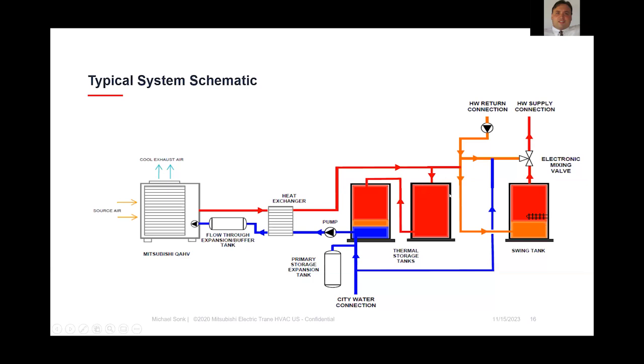So we would feed the hot water supply from this tank farm, if you will, that's been generated by the heat pump, and then into a swing tank. And that would have an electric resistance element that would provide that temperature maintenance during long idle periods. And so just like with any conventional domestic hot water system, you'd have a temperature mixing valve in that building and a heating hot water recirculation pump that would bring back hot water from the farthest fixtures to make sure you always have hot water primed out into the building. And again, the main goal here is to keep that off of the CO2 heat pumps and allow those to be utilized for what they've been designed optimally to be most efficient for, which is recharging these primary storage tanks.